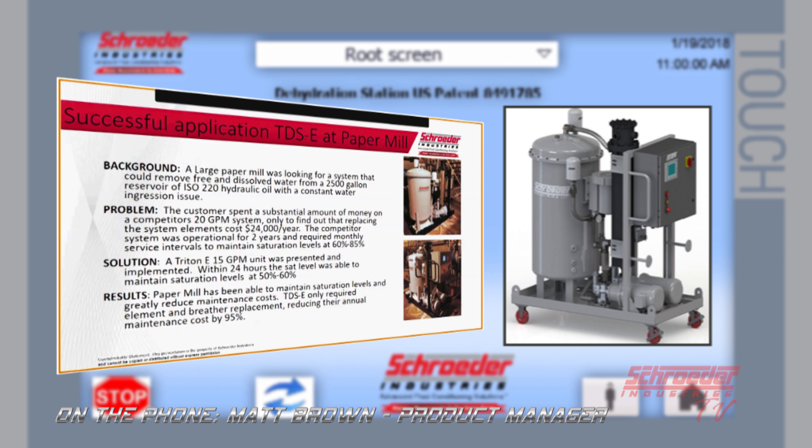We also had a successful application at a large paper mill. They had a 2,500 gallon tank of ISO 220 hydraulic oil with constant ingression of water. They had a competitor's 20 GPM filtration-type system that was costing $24,000 a year in elements and could only maintain saturation levels of 60 to 85%. We took a TDSE demo out there and within 24 hours were able to achieve 50-60% saturation and maintain it while the mill was running. They ended up purchasing that unit as well.